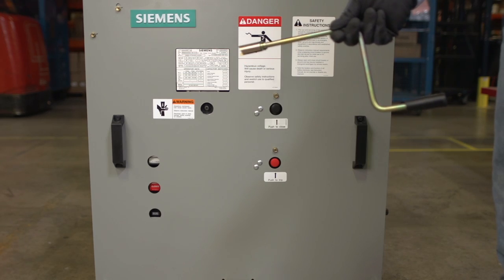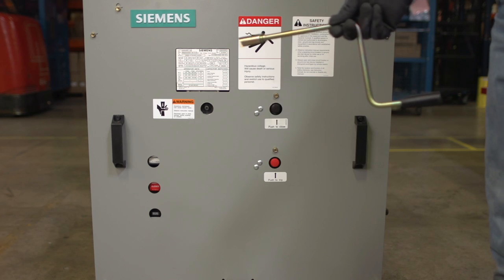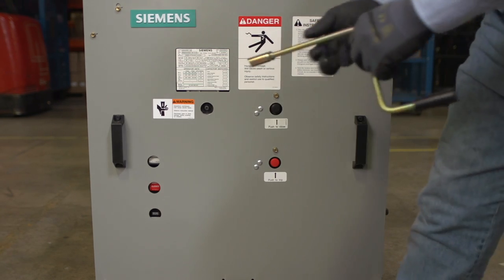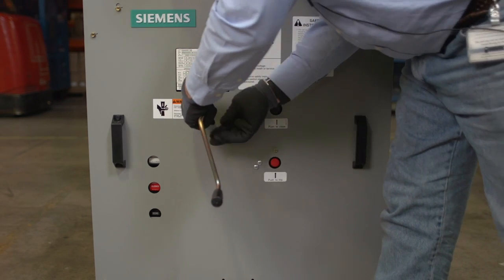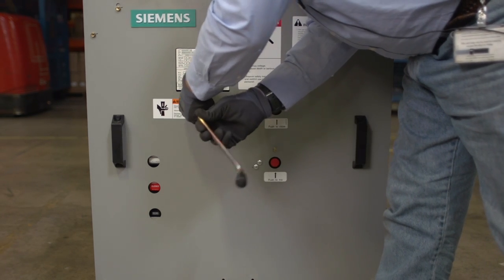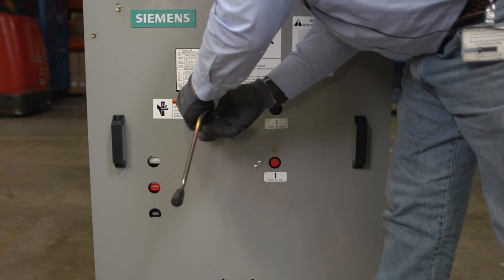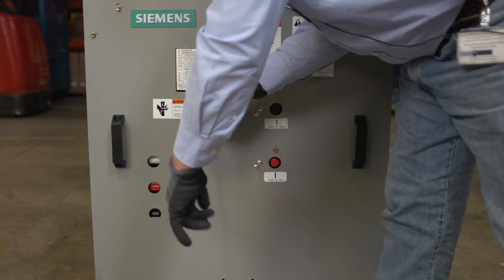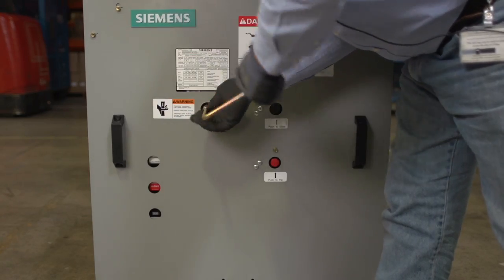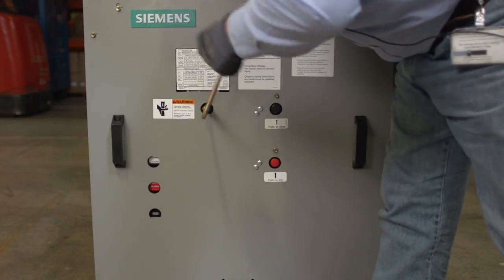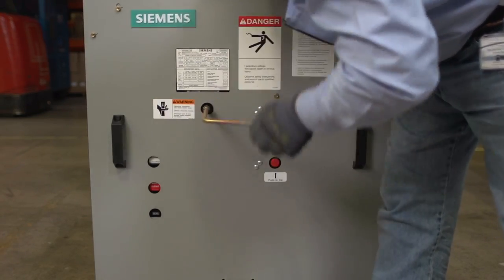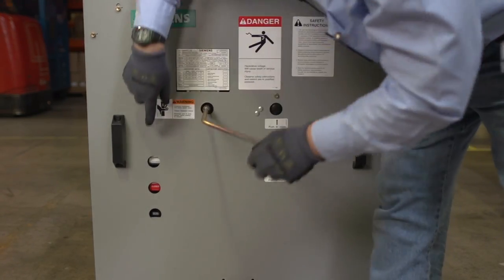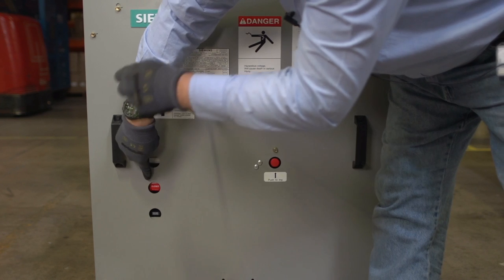Let's charge the circuit breaker closing spring using the manual crank. Insert the crank and make sure it's engaged. Begin turning to start charging. You'll notice the indicator change as the springs become charged.